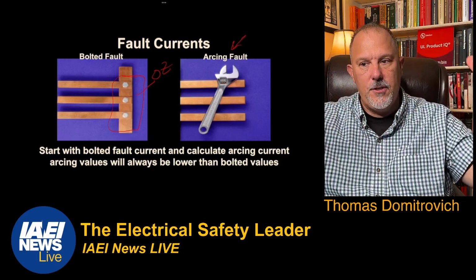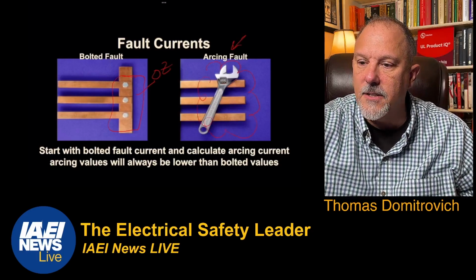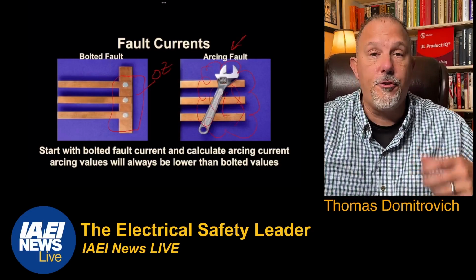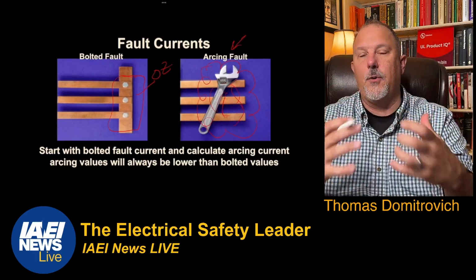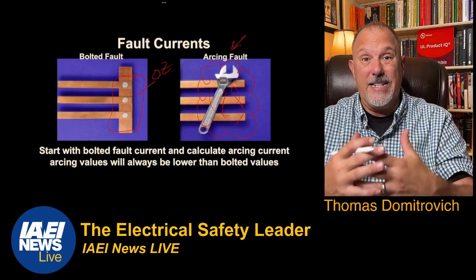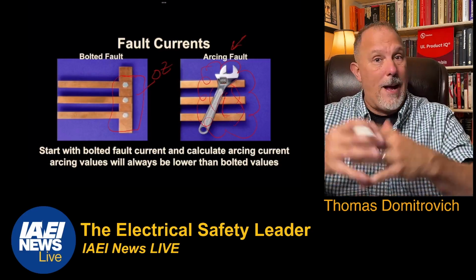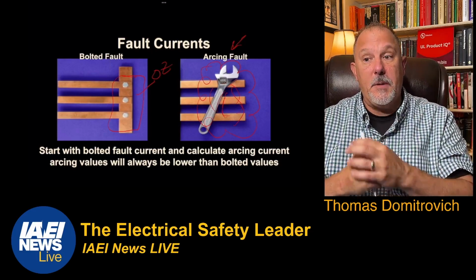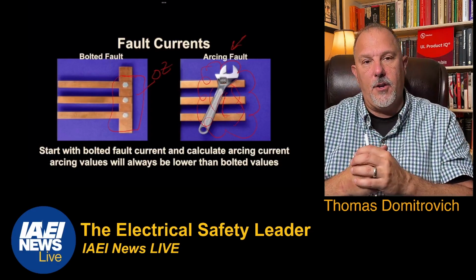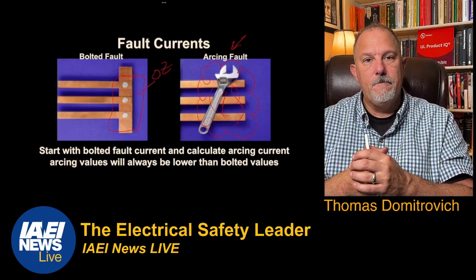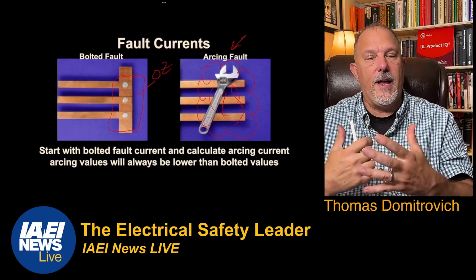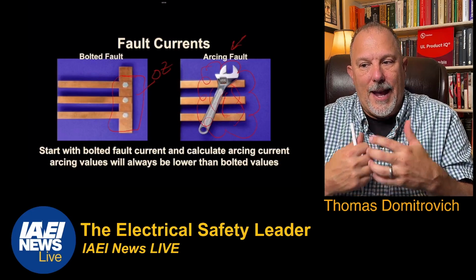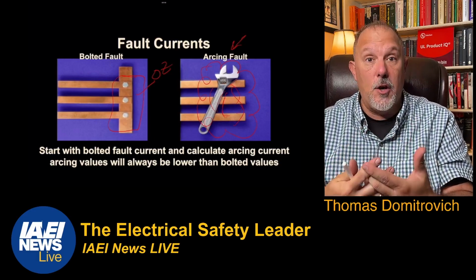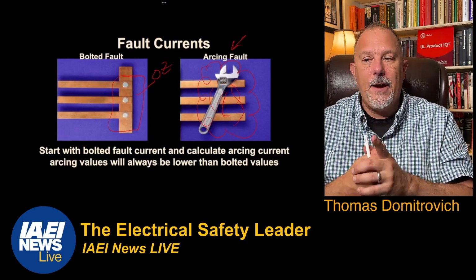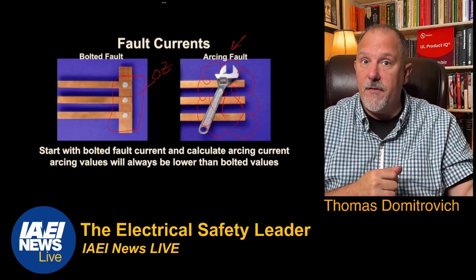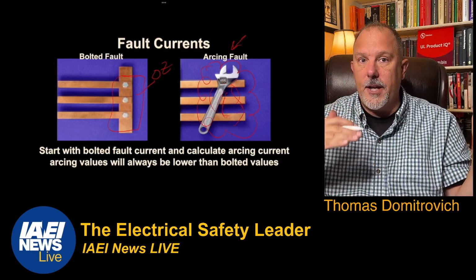And then that cloud that envelops all around those phases is going to have currents flowing through the air, phase to phase to phase, and it's going to create a lot of additional plasma and additional shrapnel and other particles to be expelled from the equipment. That copper bus is going to be vaporized, and all of that adds an impedance and gives current a path to flow basically through the air. And that will produce a lower fault current value than the 3-phase bolted fault. It will be a lower arcing current.